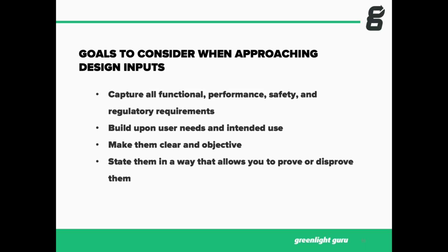If you're in V&V activities and you start making changes to the requirements, that's a very expensive time to do that. Or even worse, you launch the product into the marketplace and now you start making design changes. Those design changes could have ramifications from a regulatory perspective. They could have ramifications from a manufacturing perspective. So consider the importance of trying to be thorough, complete, and cast a wide net.